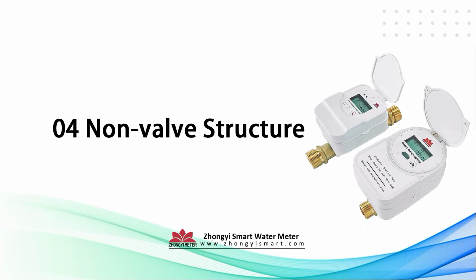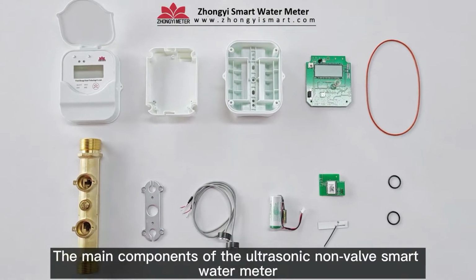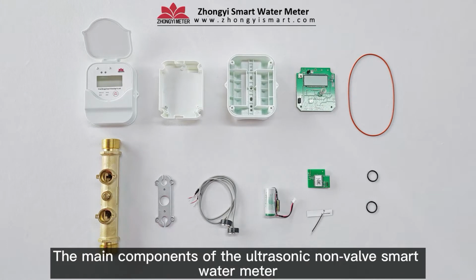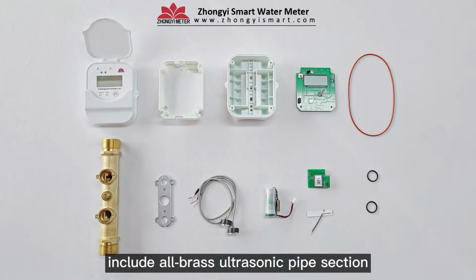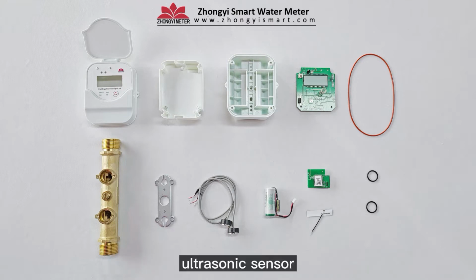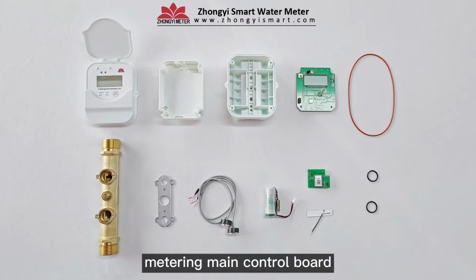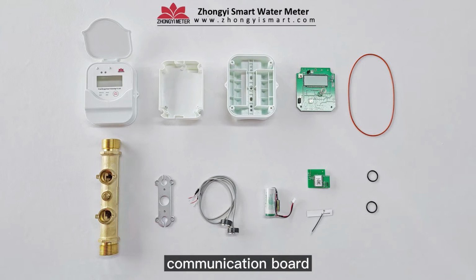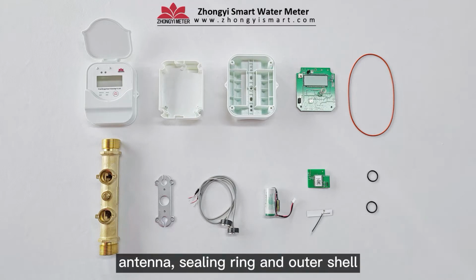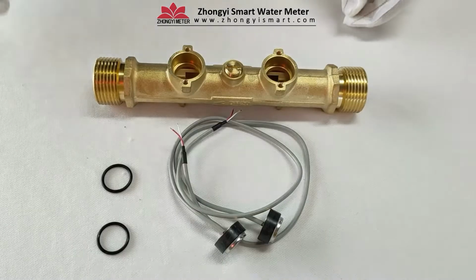Internal structure of ultrasonic non-valve water meter. The main components of the ultrasonic non-valve smart water meter include all-brass ultrasonic pipe section, pressure plate, ultrasonic sensor, battery, metering main control board, communication board, antenna, sealing ring, and outer shell.